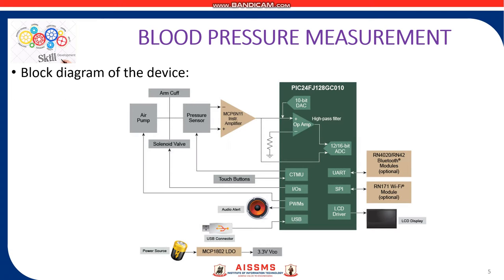Here is a block diagram of a digital blood pressure monitoring device which uses an inflatable air bladder cuff, a battery-powered air pump, and a pressure sensor for sensing arterial wall vibrations to measure blood pressure in an artery. This is known as the oscillometric method. With an oscillometric device, a cuff is inflated over the upper arm or wrist. Fuzzy logic is used to decide how much the cuff should be inflated to reach a pressure about 20 mmHg above systolic pressure for any individual.